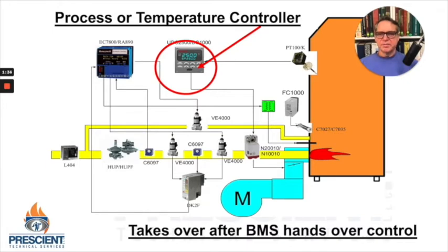Now, I'm showing you this because I've mentioned that the burner management system does no process control. It's a sentinel of safety. People talk about combustion control systems. Well, when they talk about that, you kind of got to get a little frame of reference going. And you got to talk about, are we talking about the safety side of the house? Or are we talking about the management of the flame size and the process temperature control side of the house? So generally the BMS is a safety control system, and then there'll be a process control system or a combustion control system, which will change the size of the flame and the BTU input. Now, once there's a light-off that has occurred and the BMS knows that, it hands control over to a process or a temperature controller. That's what actually then ramps and modulates and controls the firing rate control valve.